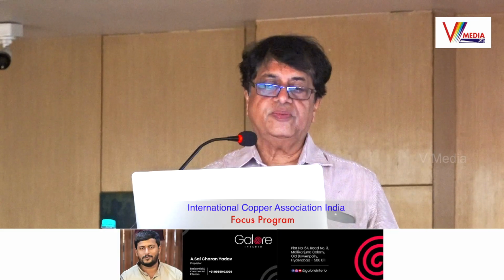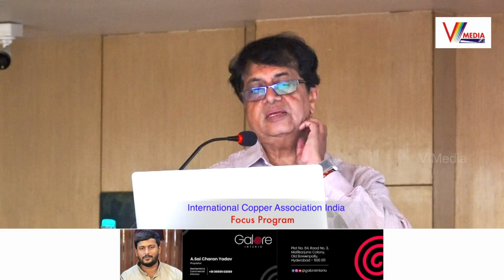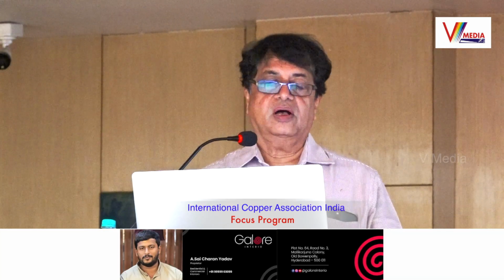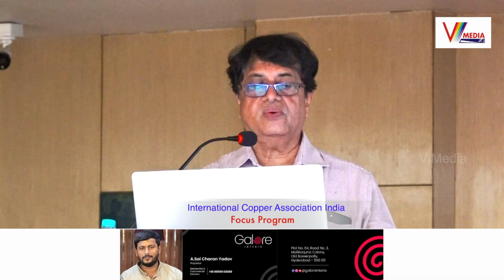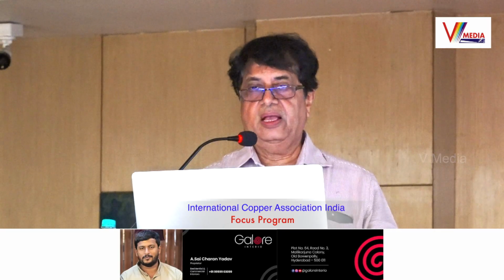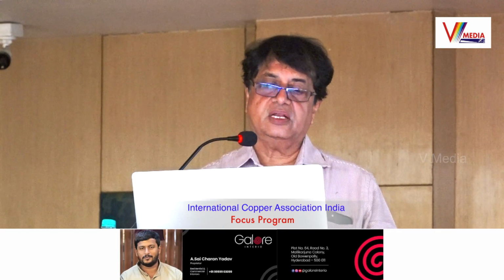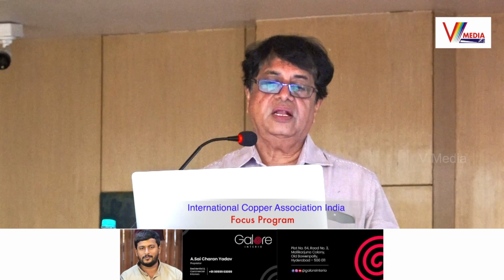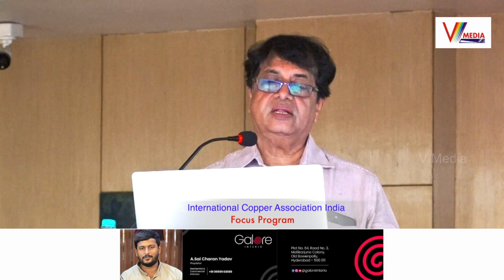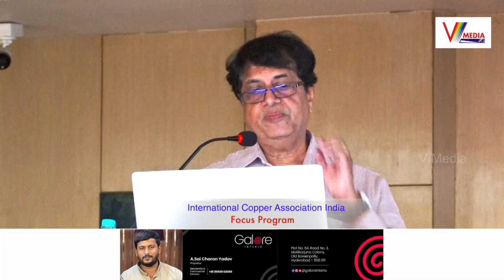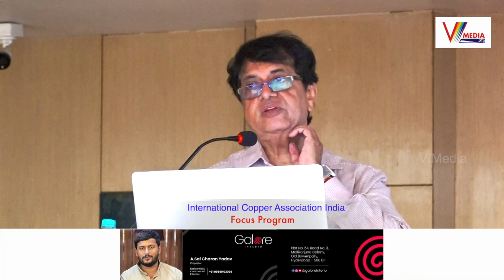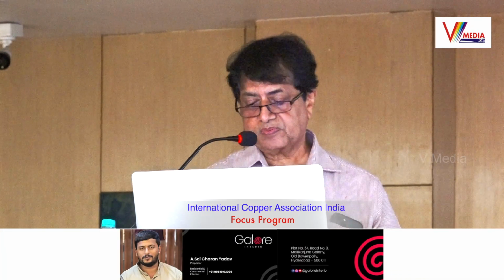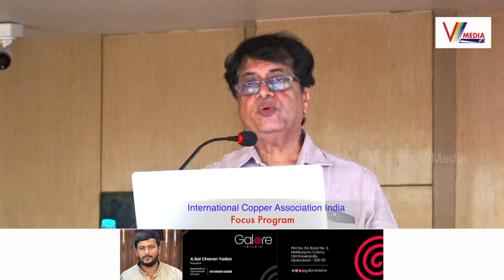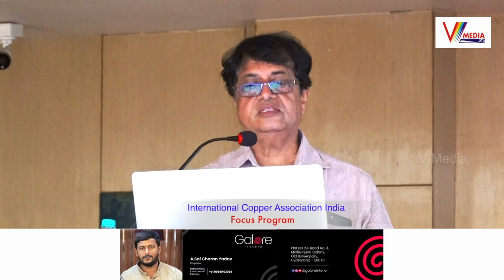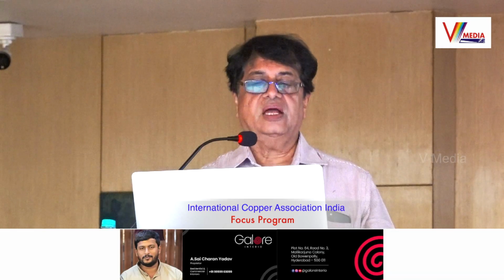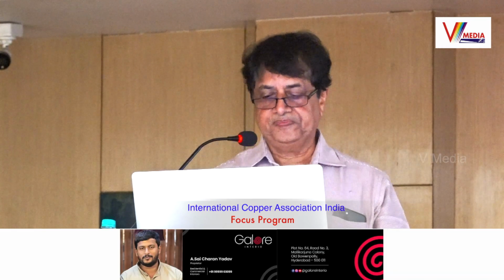So these are some pictures of the earthing pits. See the earthing pits and earthing terminals, which are constructed in the ground; those have to be accessible all the time. What happens is that during construction the earthing pits are constructed, and later some pavement is done over them and they go into hiding. If some maintenance is required, it becomes very difficult to find where the earth pit was. So it has to be accessible. It should be properly marked on the architect plans. This is the location of the earth pits, and it should be accessible all the time.